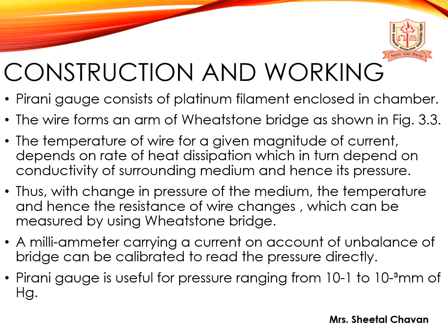Construction and working. The Pirani gauge consists of a platinum filament enclosed in a chamber. The wire forms an arm of the Wheatstone bridge as shown in the figure. The temperature of the wire for a given magnitude of current depends on the rate of heat dissipation, which in turn depends on the conductivity of the surrounding medium and hence its pressure. Thus, with a change in pressure of the medium, the temperature and hence the resistance of the wire changes, which can be measured using the Wheatstone bridge. A milliammeter carries a current on account of the unbalanced bridge and can be calibrated to read the pressure directly.